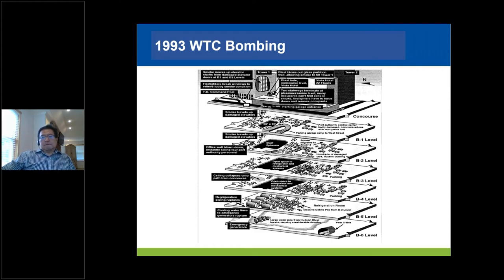From the explosion, the smoke was carried through the elevator shaft because it had been compromised, and then the smoke simply traveled throughout the tower. That happened on February 26, 1993, and because of the wintertime, there was an extremely strong stack effect in the building. The elevator shaft, going through over 1,200 feet, simply became a huge chimney, with smoke leakage everywhere in the building, making it very difficult for people to egress.